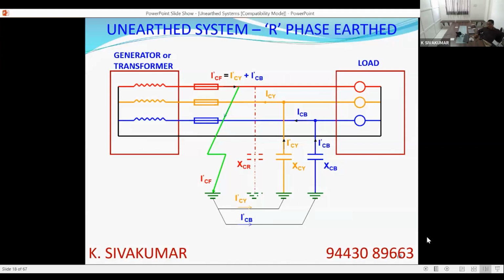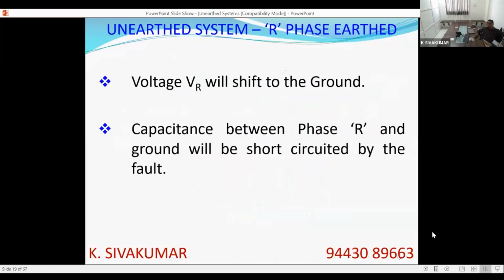But you can see XCY's ground side plate will now have the R phase voltage impressed upon it. Earlier it was neutral voltage, or zero voltage. Now it will have the R phase voltage. So also for XCB. So the capacitances XCY and XCB will receive line voltage and not phase voltage now under this condition. That is what is explained here.